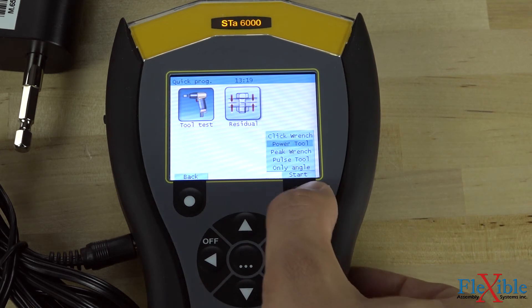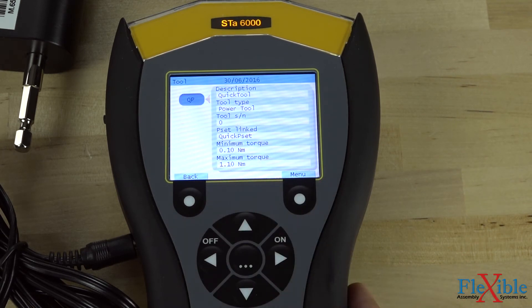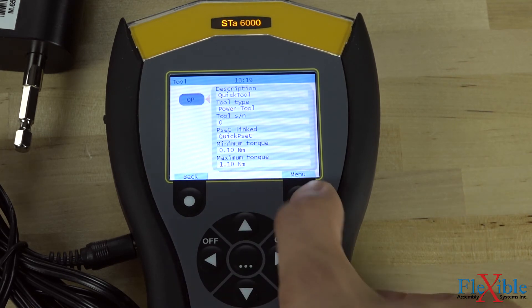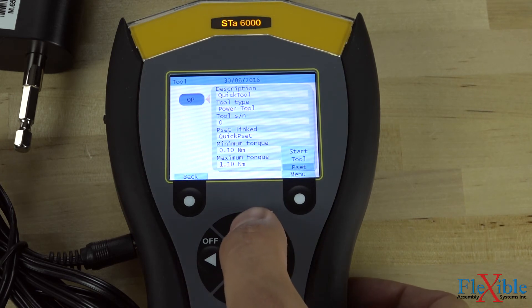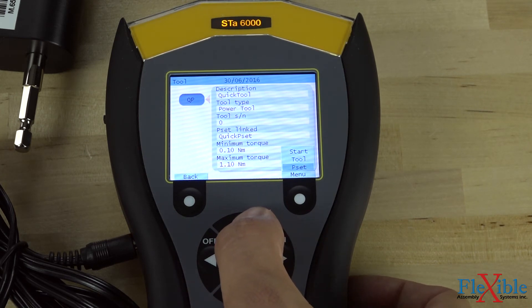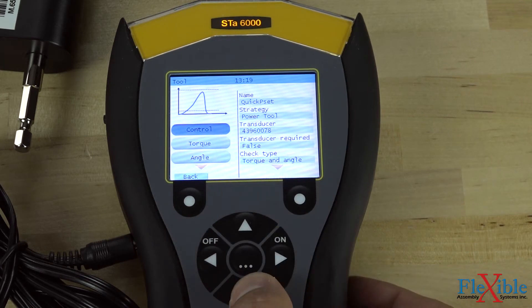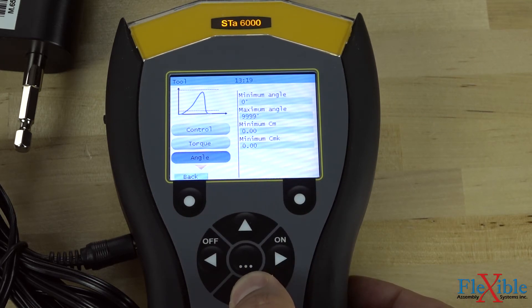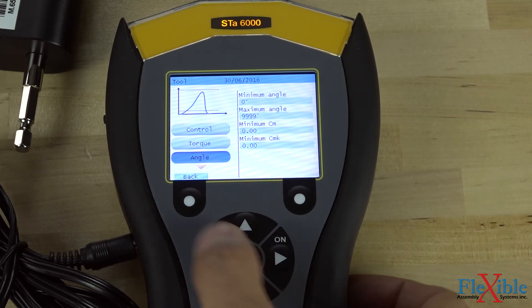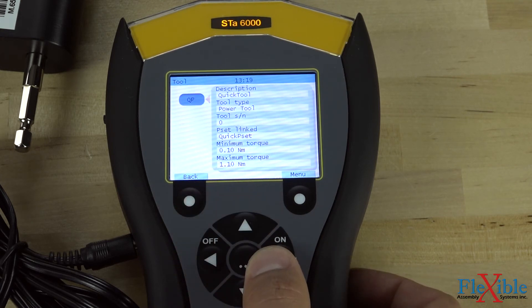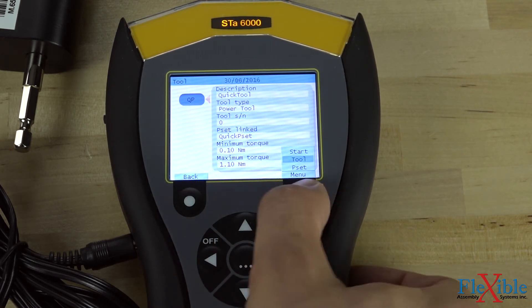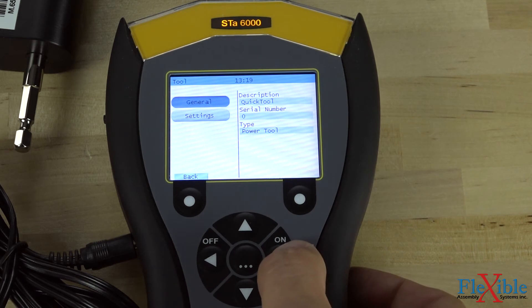After selecting power tool, we come to this screen. By hitting the menu button, we can start the test or change our tool and PSET settings. Since we are using the basic setup without an RBU, we can't save more than one PSET and don't have access to a tool database. Adding the QC or AA RBU will allow you to save up to 1000 tools in the database and up to 1000 PSETs.